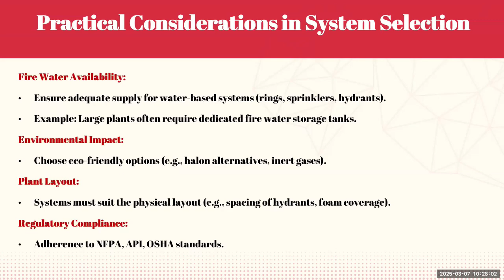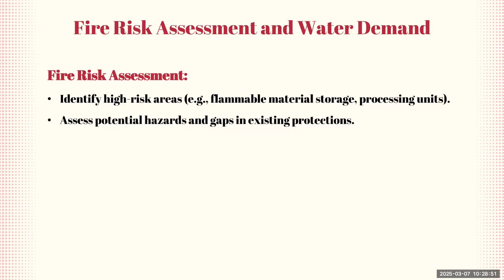Okay, now let's talk quickly. There are a lot of fire protection studies, but I would just like to show you a couple and give you a brief of why and how they're conducted. First we have the fire risk assessment and the water demand. In the fire risk assessment, we first identify the high risk areas. For example, if we have a flammable material storage or some processing units that could be prone to big fires, then these will be high risk areas. Then we assess the potential hazards and gaps in the existing protection. So we check our current protection and determine what are some weaknesses and gaps in our current protection systems.